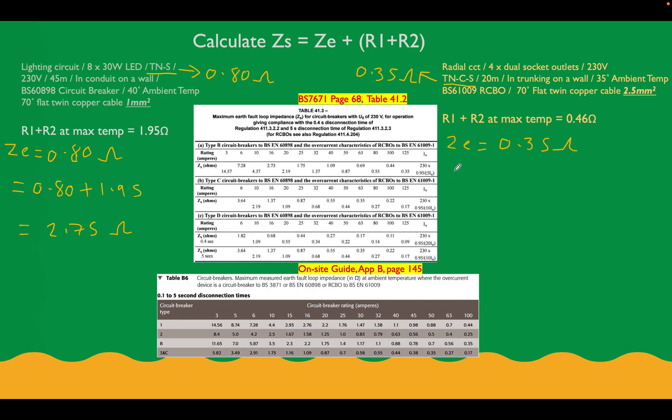Let's go on this side and do the same again. So this is going to be equal to 0.35 plus 0.46, which is our maximum ZE plus our R1, R2 value, and that's going to be equal to 0.81 ohms. So that's our ZS value for the radial circuit. Perfect. Let's underline those so we can recognize those afterwards.